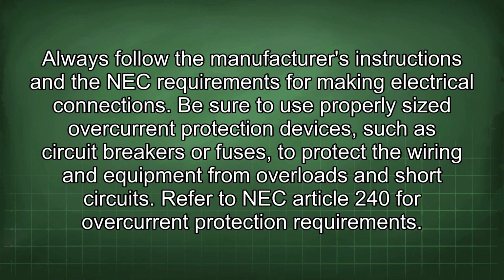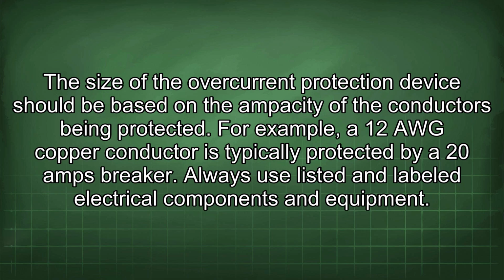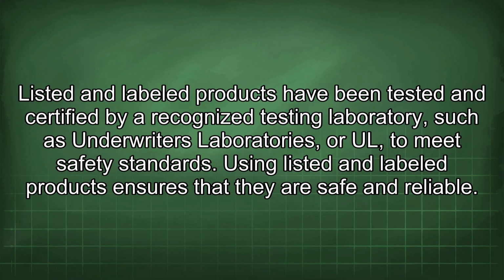Be sure to use properly sized overcurrent protection devices, such as circuit breakers or fuses, to protect the wiring and equipment from overloads and short circuits. Refer to NEC Article 240 for overcurrent protection requirements. The size of the overcurrent protection device should be based on the ampacity of the conductors being protected. For example, a 12 AWG copper conductor is typically protected by a 20 amp breaker. Always use listed and labeled electrical components and equipment. Listed and labeled products have been tested and certified by a recognized testing laboratory, such as Underwriters Laboratories, or UL, to meet safety standards. Using listed and labeled products ensures that they are safe and reliable.